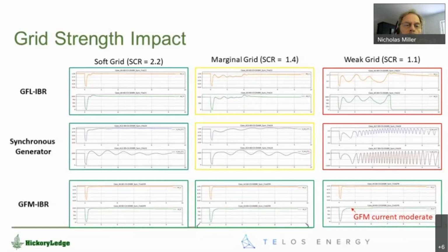In the middle is all of the things being identically equal with a synchronous machine, and those wiggles will look quite familiar to you. You see the damping gets worse, the post-fault recovery voltage is uglier in the yellow case, also a violation of criteria. And then on the right, you have loss of synchronism, a classic pole-slipping case.